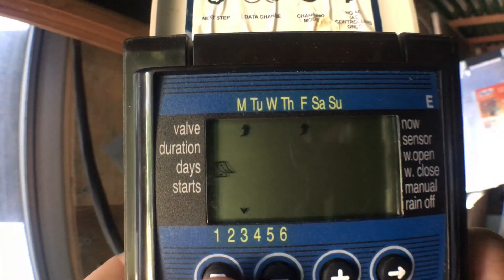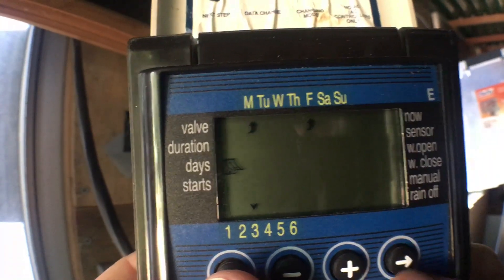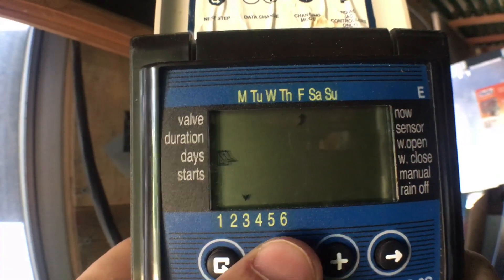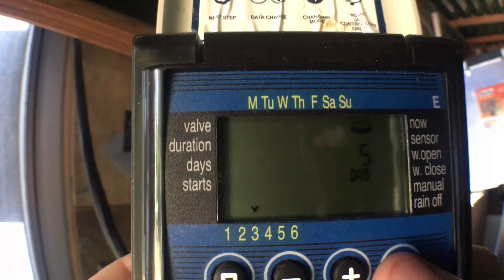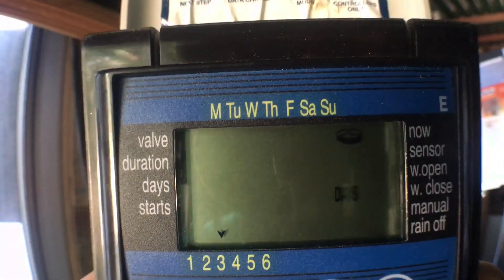Then there's the manual function again. To review: I select the valve, select my duration of one hour 35 minutes, Monday and Friday. If I wanted to change back to cyclic — say every five days is a better interval than picking days of the week — I can hit my arrow and cycle past it. I can also delete days: while a day is blinking, I hit minus to empty it. Removing Monday and Friday takes me back to cyclic mode. I'll change that to every four days since it's getting a little dry out there. That's set for valve three.